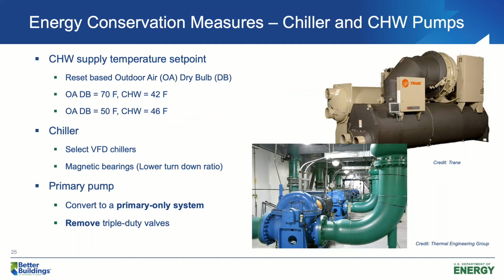When the outdoor air temperature is 70 degrees or higher, we can make the chilled water temperature 42 degrees. When the outdoor air temperature is 50 degrees or lower, we can make the chilled water temperature 46 degrees, and we can do linear regression in between. This way, we can have a good balance between chiller energy and pump energy.